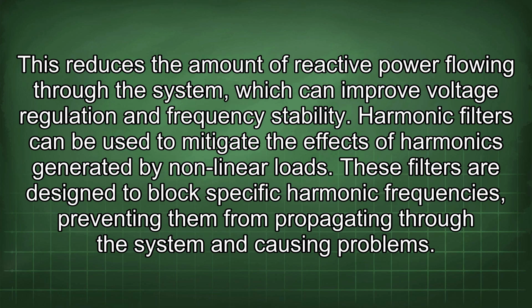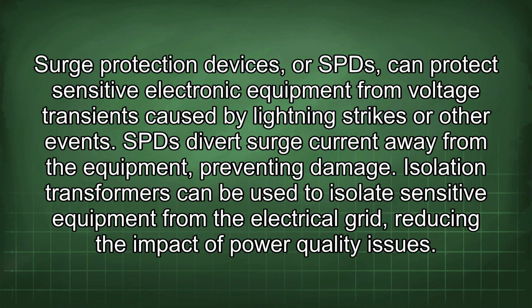Harmonic filters can be used to mitigate the effects of harmonics generated by nonlinear loads. These filters are designed to block specific harmonic frequencies, preventing them from propagating through the system and causing problems. Surge protection devices, or SPDs, can protect sensitive electronic equipment from voltage transients caused by lightning strikes or other events. SPD diverts surge current away from the equipment, preventing damage.